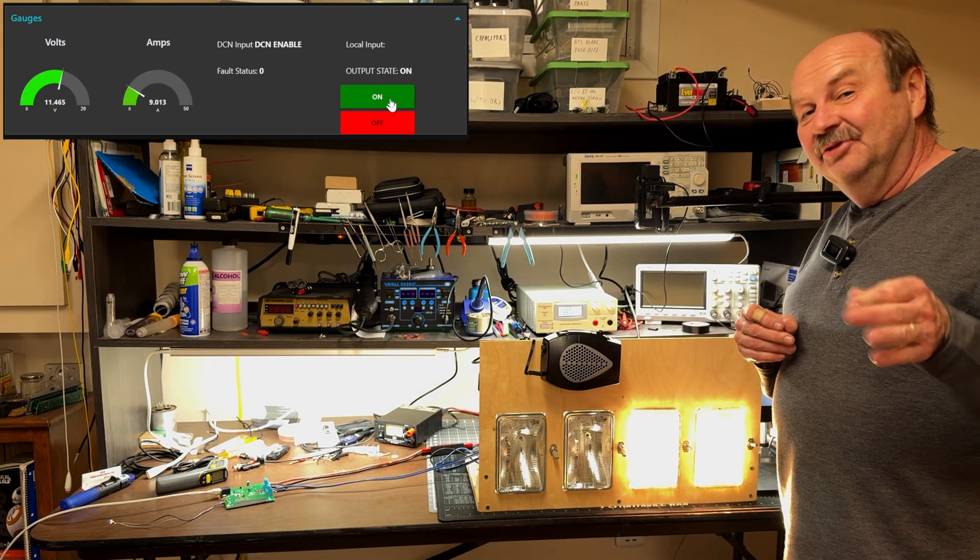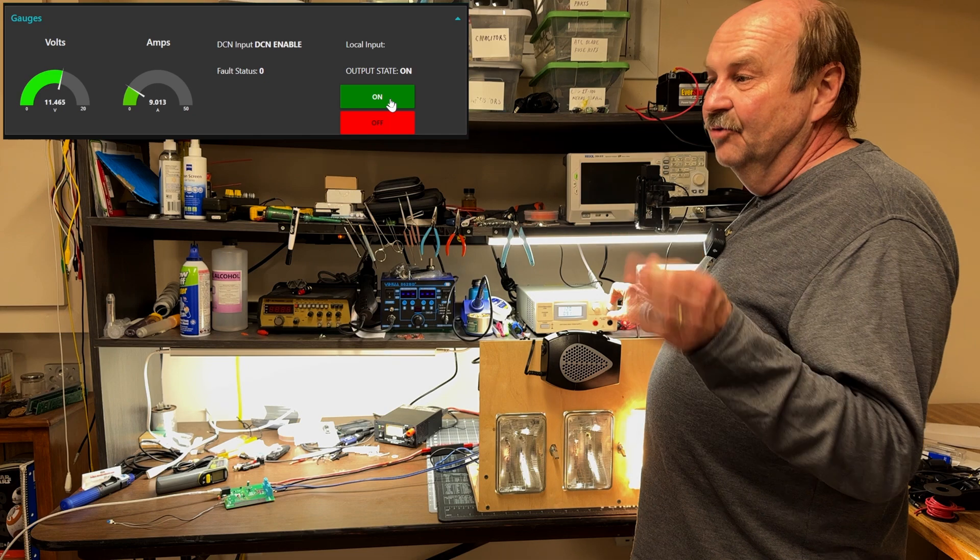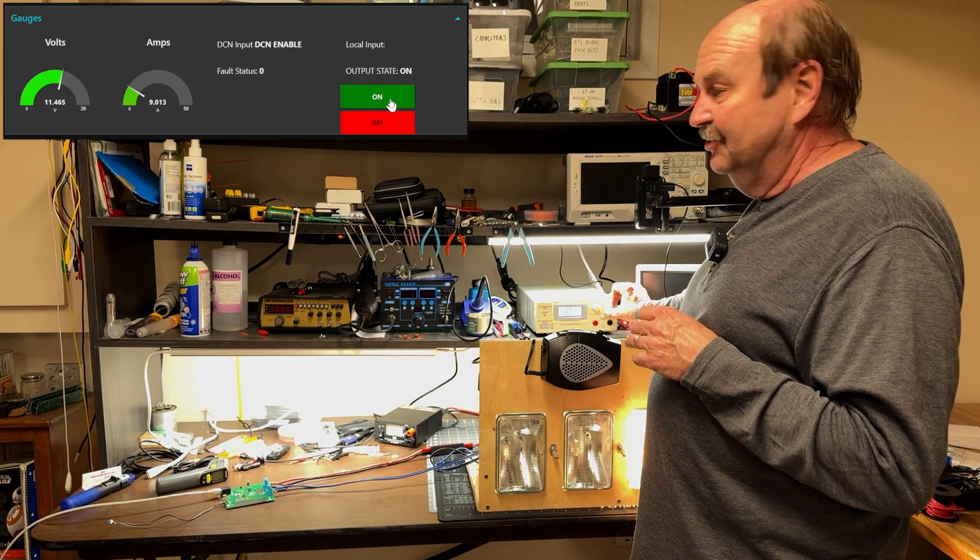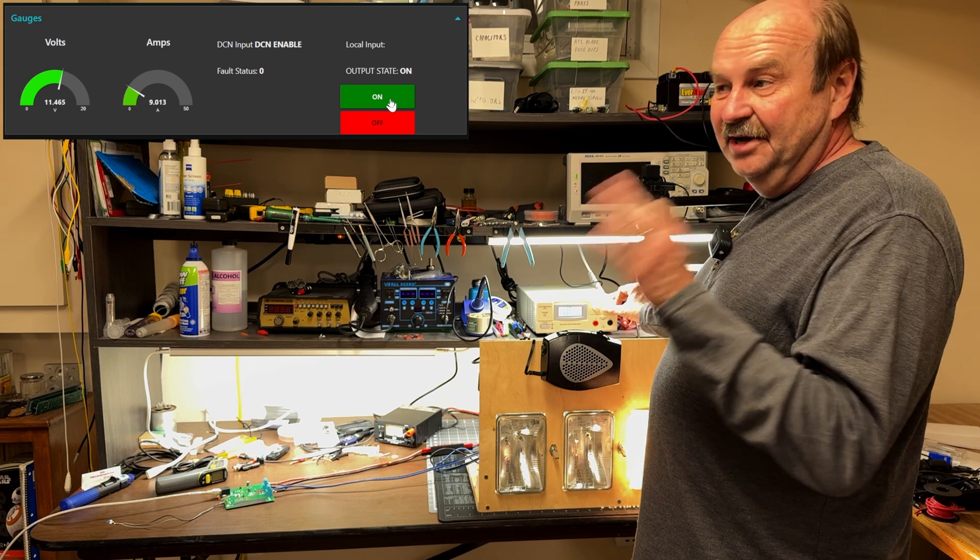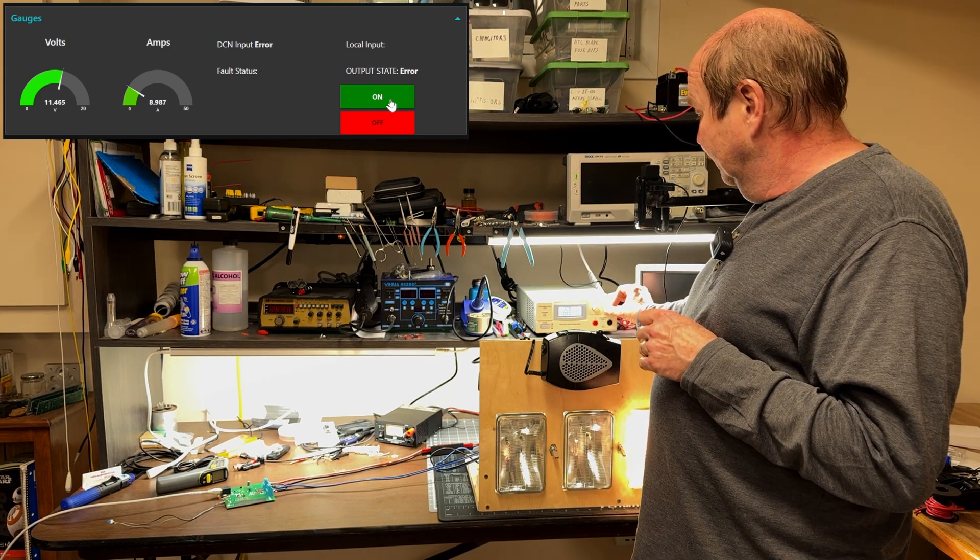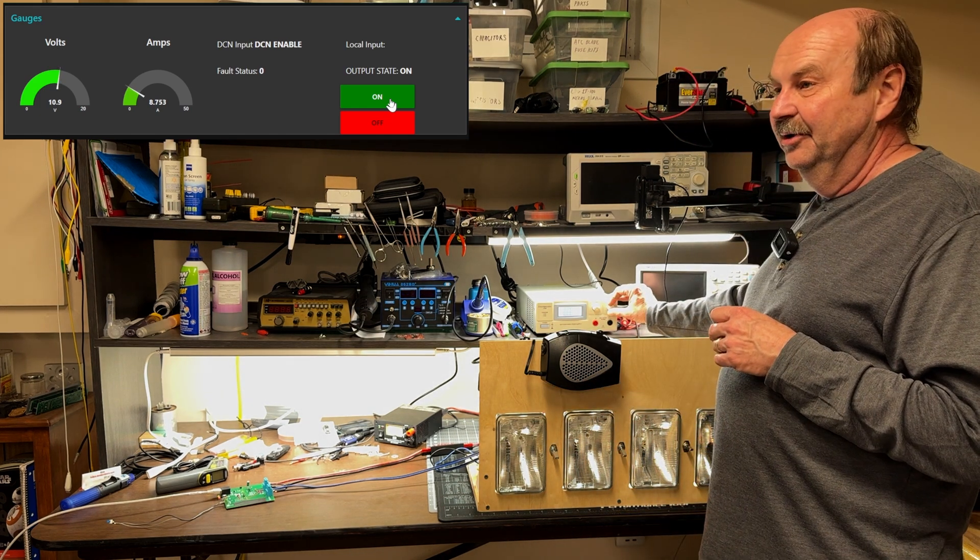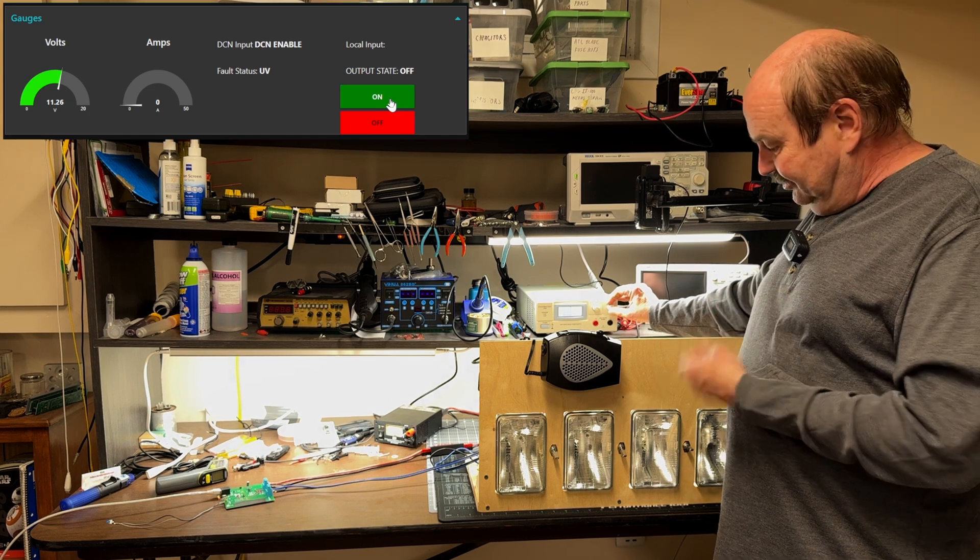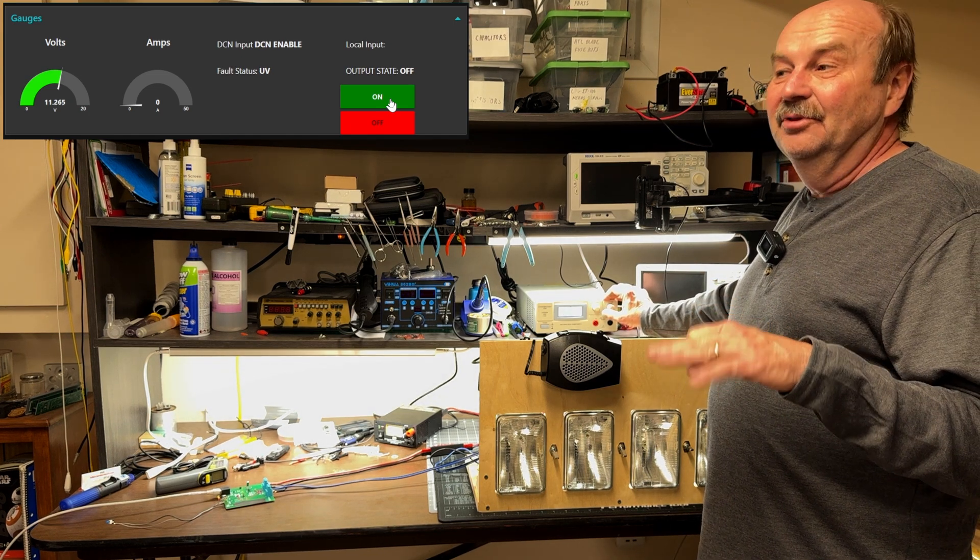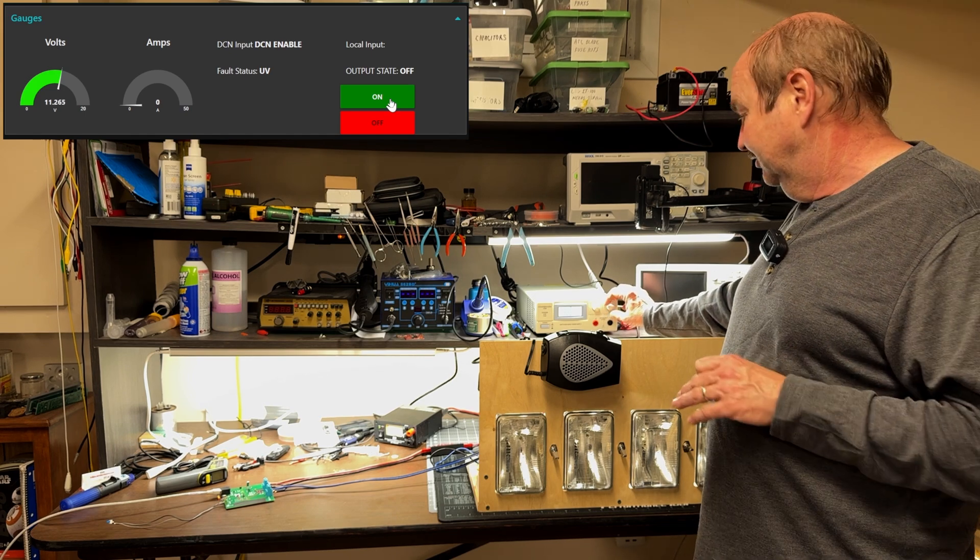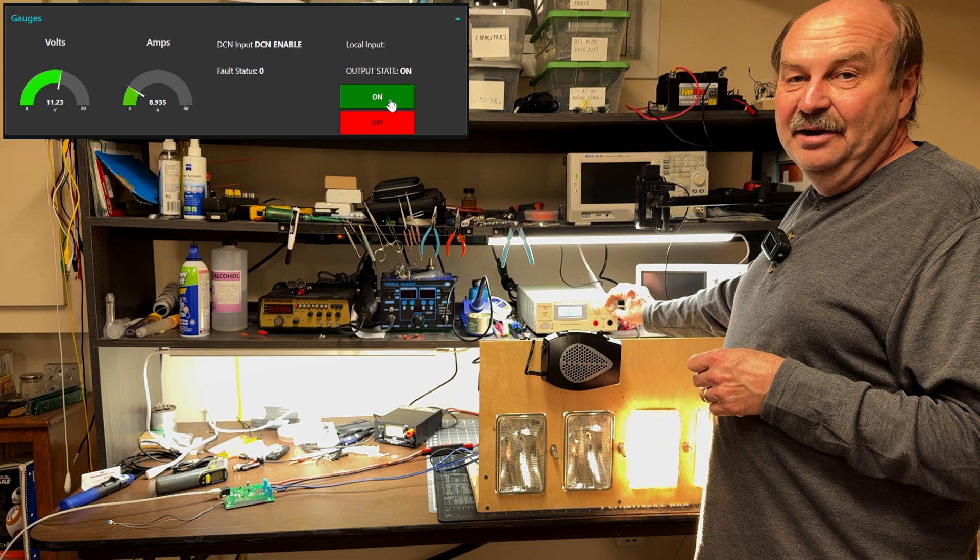Now, the other features that this has is over and under voltage. So, I'm going to take my power supply here. I've got the under voltage trip set on this for 11 volts right now. And if I start turning this down, you'll see the lights are dimming a little bit here. There, I got to the trip point, and it shut off. Now, the under and over voltage trips, those are set up to always automatically restart. So, if I bring the voltage back up, it comes back on.